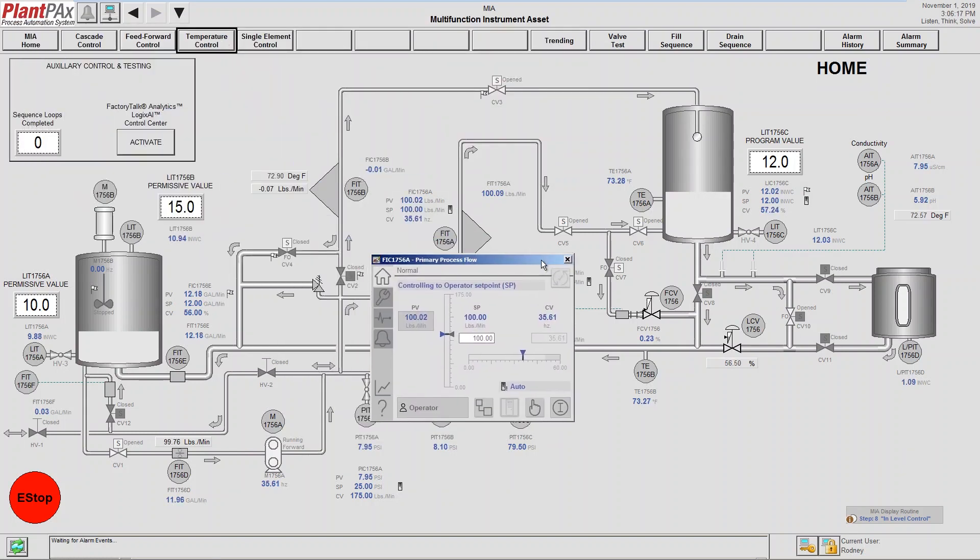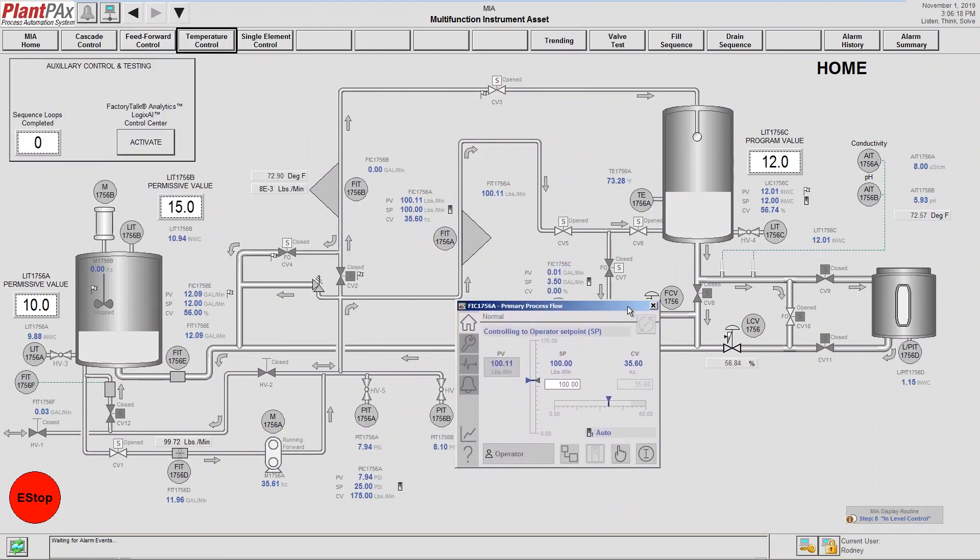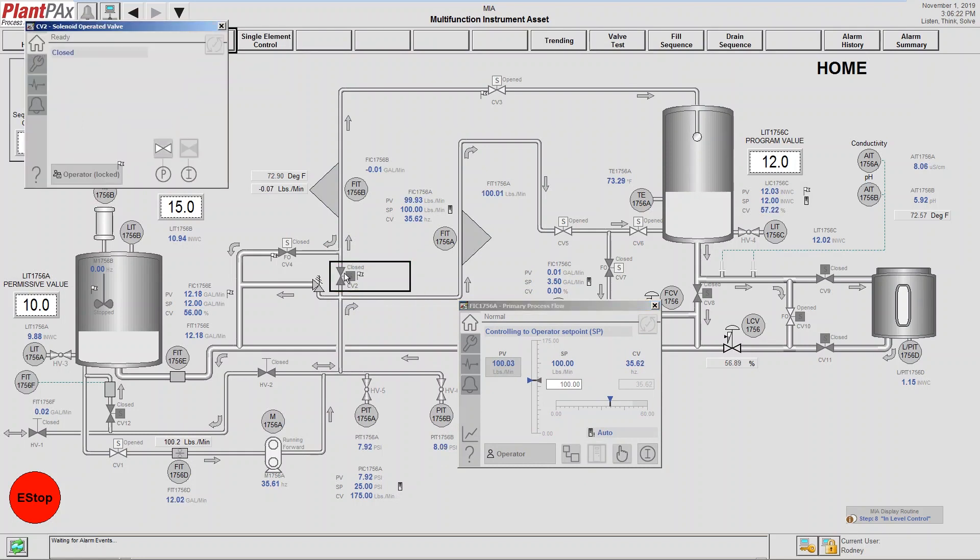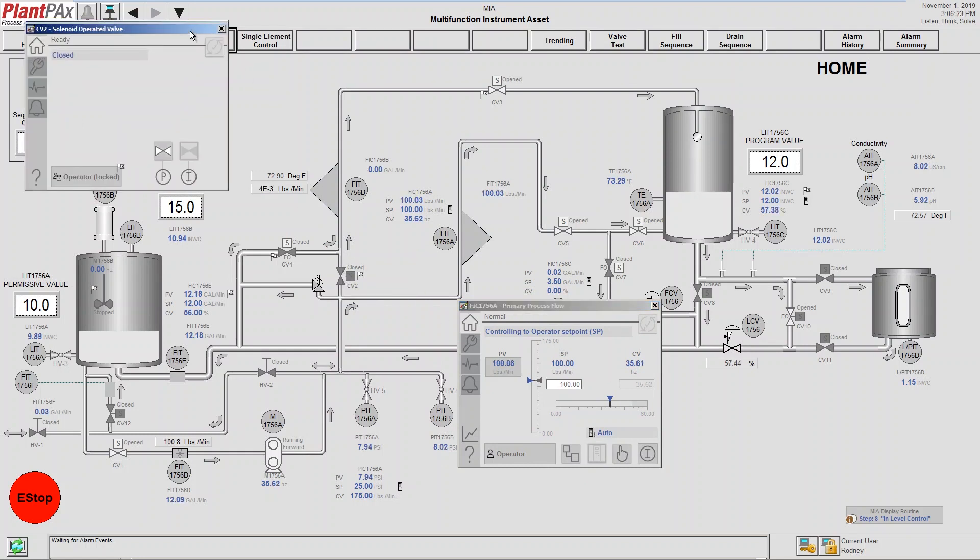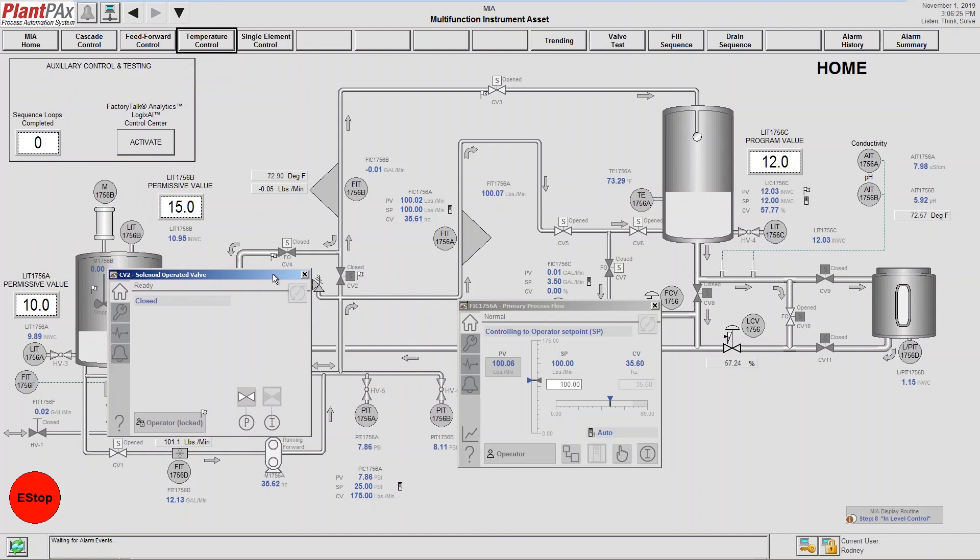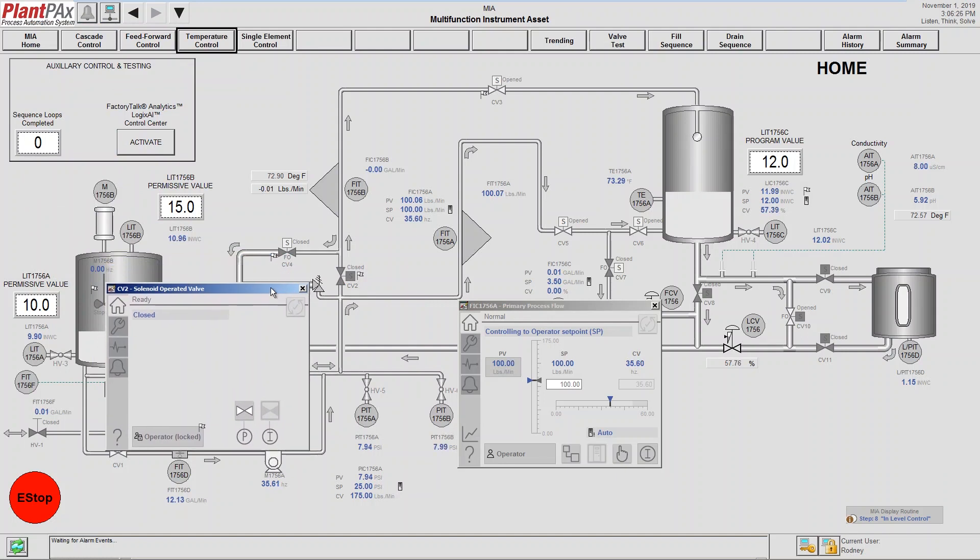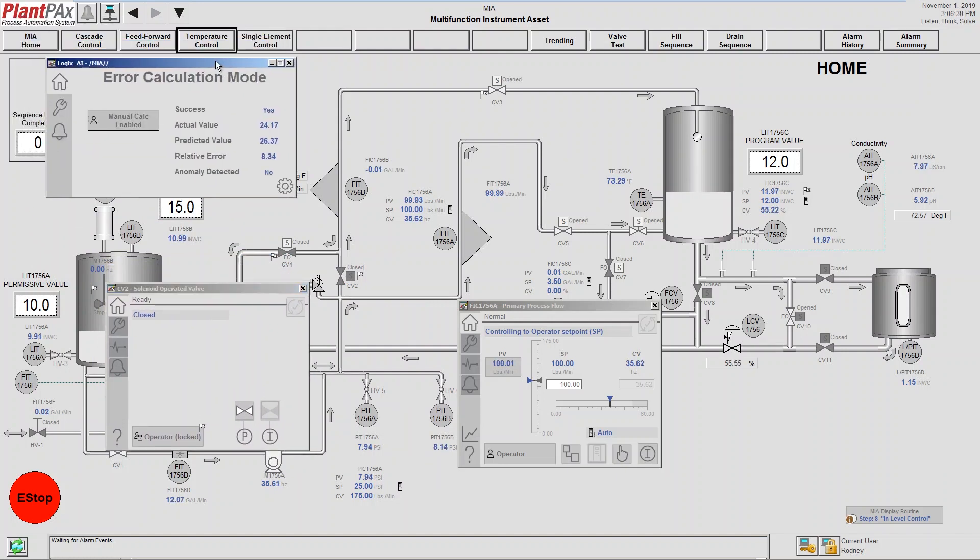With that, we're going to move into the actual calculation mode, where we can test if we have an anomaly. The anomaly will tell us something is different from what the model actually learned. When we get set up, we're actually going to bypass water around our model. So the model is looking at the primary flow.